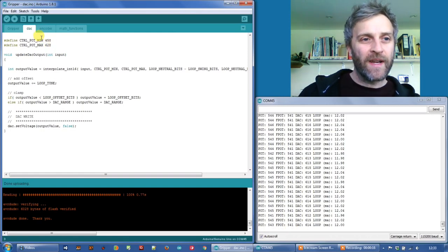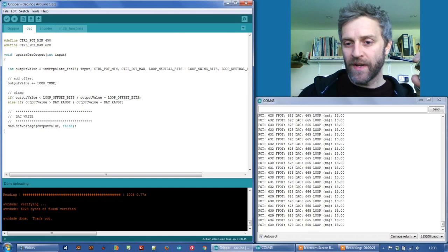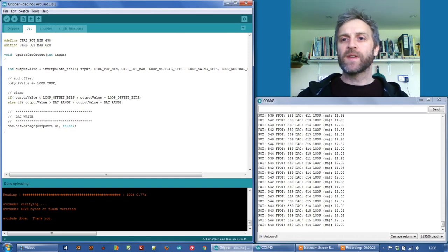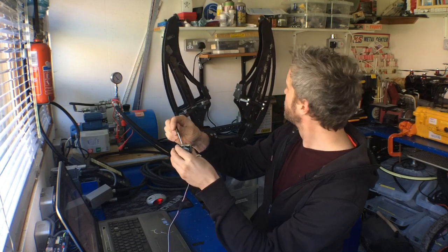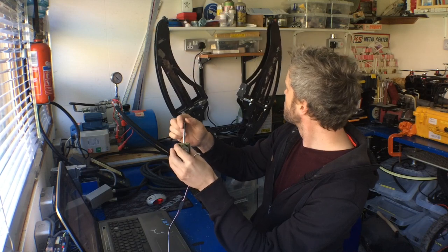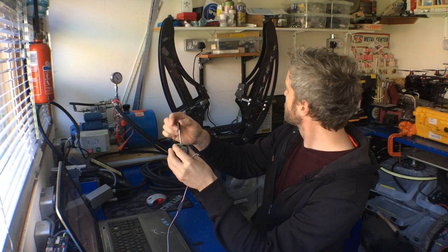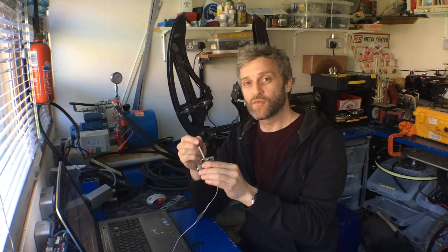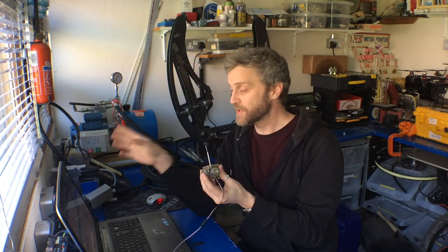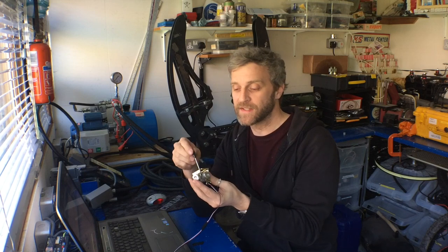So I fed those back into my control pot minimum and maximum, so that I get a nice swing on my output of 13 milliamps to 11 milliamps. And now that's in place, we can check out how it works on the gripper again. That's pretty good. So we're getting the full range of travel now, and that was still only plus and minus 1 milliamp on the valve, so it's 1/8 of its full flow capacity.